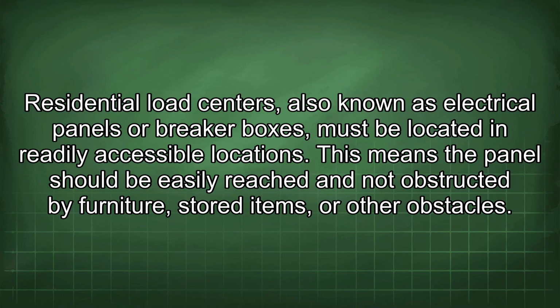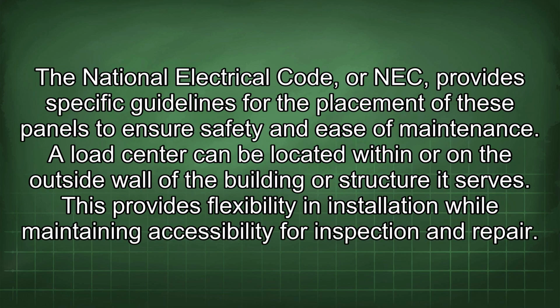Residential load centers, also known as electrical panels or breaker boxes, must be located in readily accessible locations. This means the panel should be easily reached and not obstructed by furniture, stored items, or other obstacles. The National Electrical Code, or NEC, provides specific guidelines for the placement of these panels to ensure safety and ease of maintenance. A load center can be located within or on the outside wall of the building or structure it serves. This provides flexibility in installation while maintaining accessibility for inspection and repair.